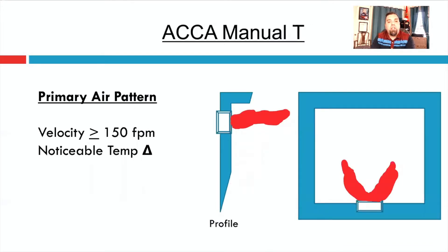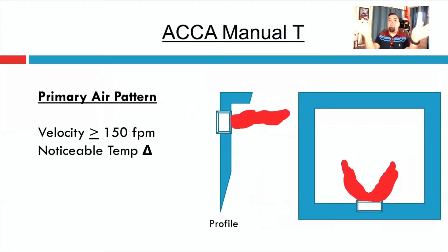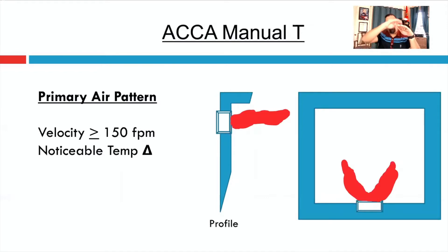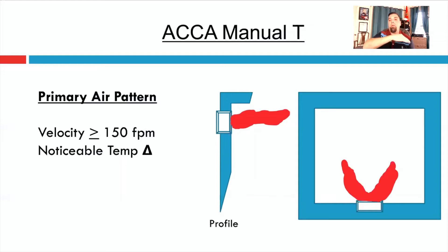When we locate a register in a room, there are a couple of things to talk about. First, the primary air pattern. If you look down on the room in a profile view, the primary air pattern in heating is what you planned — for example, a high-wall register in the middle of the room to easily throw the correct distance and mix the air. Typically you'll find that the heat starts to rise, and what ends up happening is it'll pull that air pattern up as it moves along. That is what's called the surface effect — you have low pressure right above close to the register, right above that primary air pattern, and that surface effect is going to pull that warm air up to the ceiling.